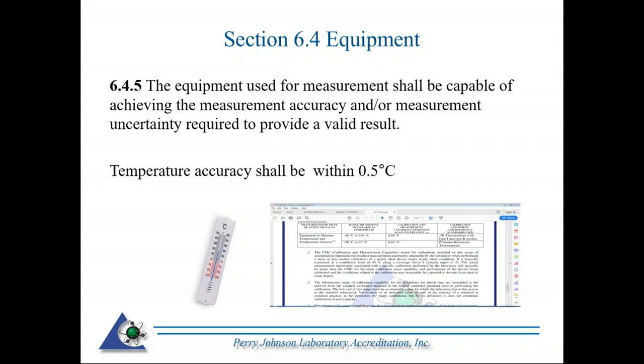That's another name for the best uncertainty that the calibration lab can produce. So in other words, if you had that accuracy requirement and you're sending it to a facility that had that on their scope of accreditation, that's the best they're going to be able to produce for you under their scope of accreditation. So they're not going to give you an uncertainty less than 0.66. So if you needed your device to be within 0.5, this particular example of this organization would not be able to meet those requirements.